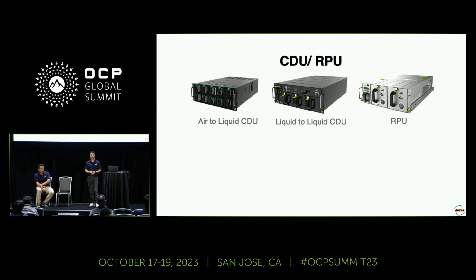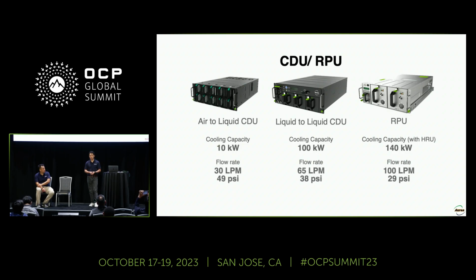So currently we have 3 different product lines. The first one will be the air to liquid. The second one is liquid to liquid, and the third one is RPU. The cooling capacity ranges from 10 kilowatt to 140 kilowatt across the different product lines. And here shows you the flow rate, which is 30 LPM to 100 LPM. With the air to liquid, it has a fan tray at the front, so it can support up to 600 CFM.